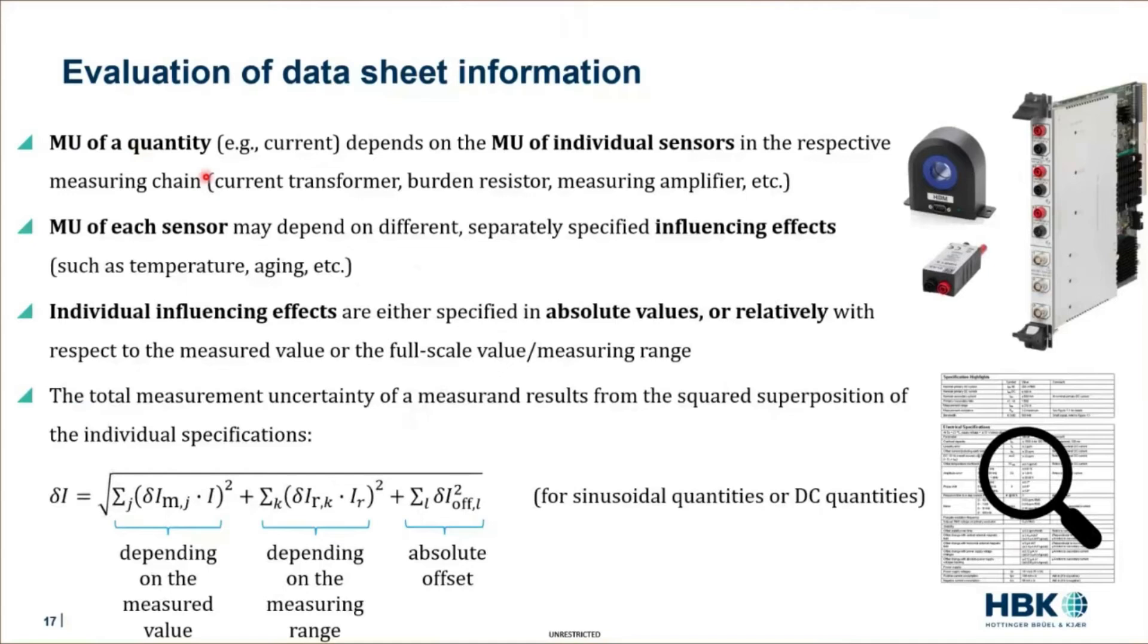In order to measure the current, we have a lot of different sensors in the measuring chain. For example, the current transducer, the burden resistor and the input amplifier or the power card in this case. And all of them contain measurement uncertainty, in addition to the environmental conditions. What we should do is we need to calculate the measurement uncertainty of all of those components. And then each component, if you look into the data sheets of those components, each component is specified with different influencing effects. If I say influencing effects, I talk about things like temperature, temperature depending errors, aging dependent errors, nonlinearity error or magnetic field influence and all those things.